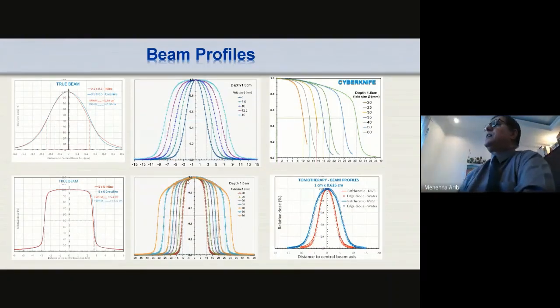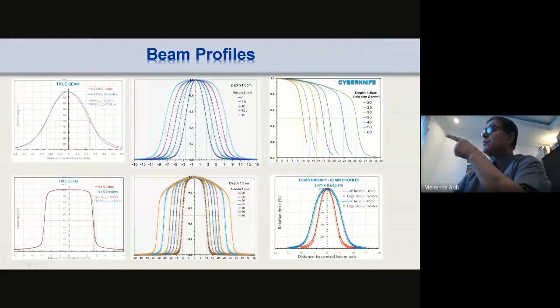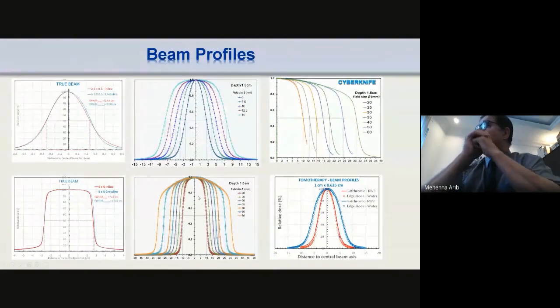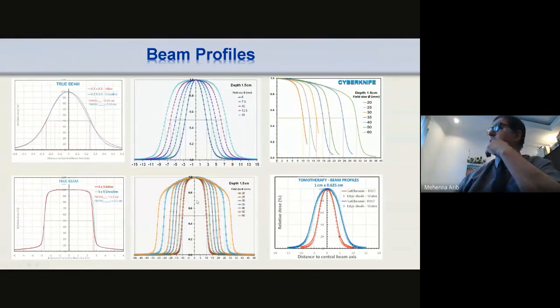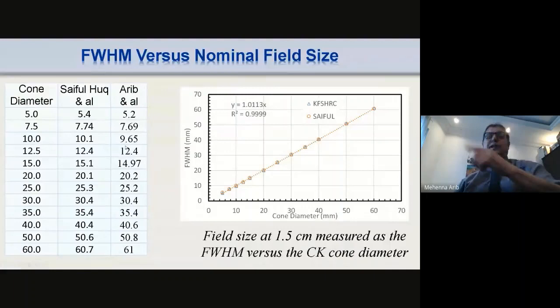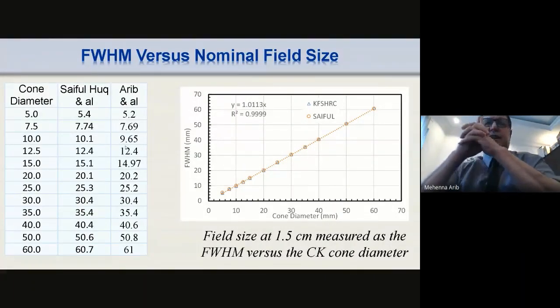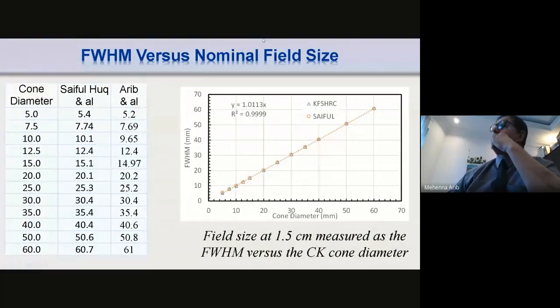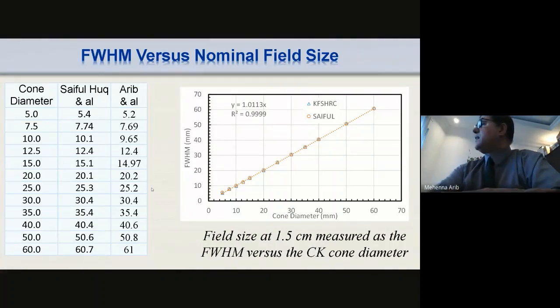So these are the measurements we did for True Beam, for Cyberknife, and for tomotherapy. And we did also, so look at this. For Cyberknife and tomotherapy, these are FFF field sizes. So from these curves we can calculate your full width at half maximum, and then I just display here. We worked in parallel with the group of Saiful Huq in USA. So you have here the cone diameter of the Cyberknife, and you have the full width at half maximum, the S-clin, the full width at half maximum calculated or obtained from the profiles. You see that you have a linear behavior, which is good for both our two groups.